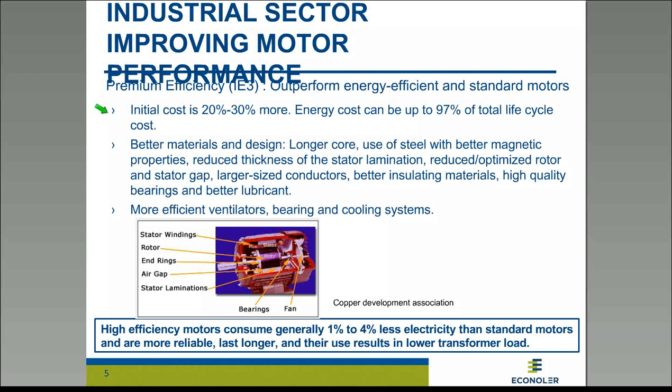system. So several motor system studies have demonstrated that energy costs can be up to 97%, but typically we see several applications where energy cost over the life of the motor is 80% to 90% of the life cycle cost, including the capital purchase of the motor initially, then operating costs.